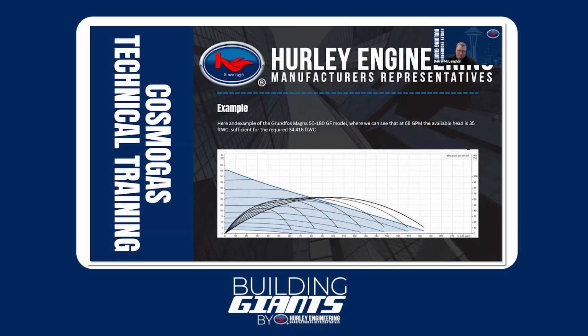So it's got to be addressed. And if you do a little bit of legwork on the front end, then your success with these boilers will be amazing. I've seen a boiler that was running for almost 2 years or a little more, and the water side and the fire side were not dirty at all. It looked almost brand new. So it just shows what's possible if it's sized and designed and installed appropriately.